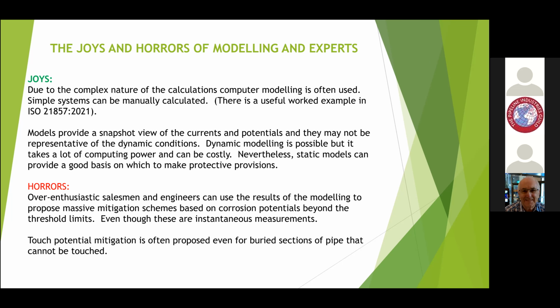If there's nothing for them to touch in that section where there's 70 or 100 volts, there's no need to do anything. It's only if there's something they can touch that they'll get an electric shock. Even if there is a test post there, you can easily install a dead front test post, which is cheap and prevents anybody touching the connectors. So that fulfills the requirements for touch protection, and you don't need to do an expensive voltage drain exercise on the pipe.